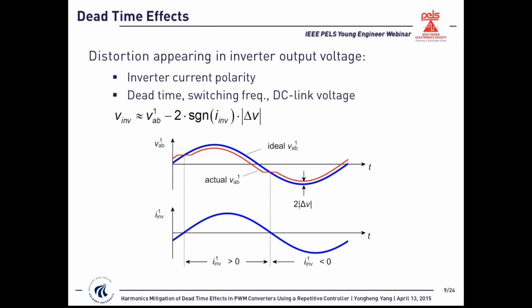As I mentioned, this voltage distortion appearing in the inverter output voltage is related to the inverter current polarity, and the voltage distortion level is affected by the dead time duration, the switching frequency, and also the DC link voltage. This figure illustrates how the inverter current polarity will affect the voltage distortion of the inverter output voltage.